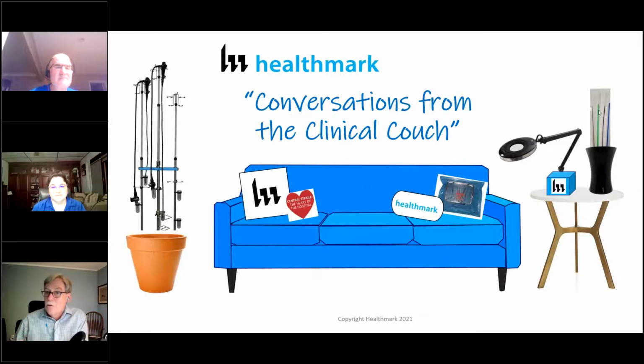And it's that filtered forced air drying, whether you use active drying before you put it into a cabinet or you have a drying cabinet that allows for continuous drying. That's going to be a change, and that's going to be an expense, if you will, a transition for endoscopy units, and extra time in the process, because many facilities will make sure their scopes are dry before they go into the cabinet, but not really worry about it if they're going back out to be reused right away. So that could be a big process change for a lot of facilities.